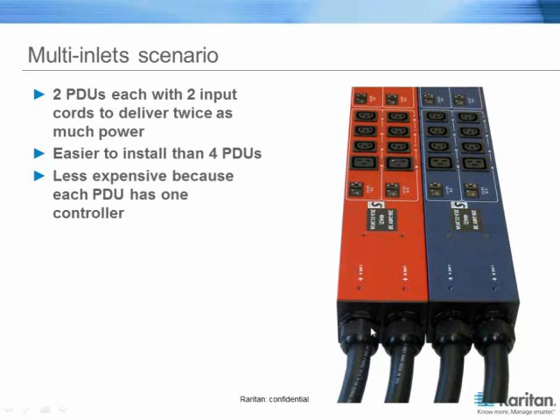Right now, this is considered 2 individual feeds, but one of the advantages here is each PDU is sharing a brain. So instead of having 2 or 4 different PDUs depending on your deployment, we have either 1 or 2 double input PDUs coming into your rack or racks, and that PDU is sharing a brain, sharing the sensor ports, sharing that common intelligence. So there will be a less expensive price to deploy a multiple inlet PDU because it's sharing those resources versus having a PDU with individual resources.